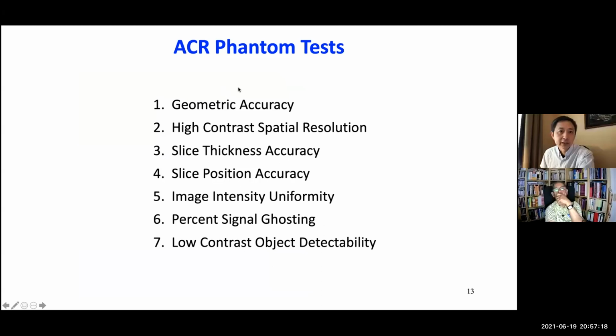So the ACR phantom can typically provide 7 kinds of testing: geometric accuracy, high contrast spatial resolution, slice thickness accuracy, slice position accuracy, image intensity uniformity, percent signal ghosting, and low contrast detectability. I will give an example for each one of them.